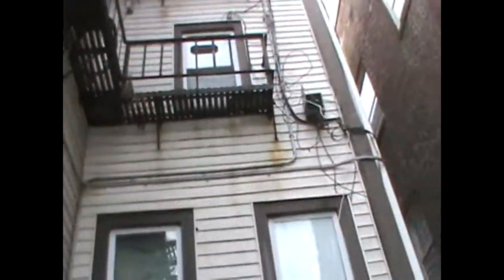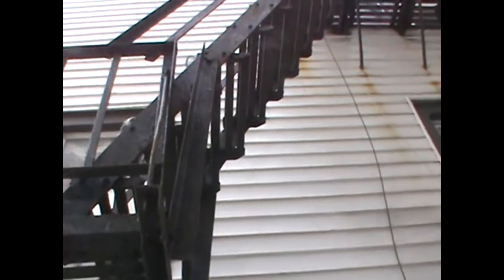So now look at these connections that hold the thing into the building. Any of these suspect? Sure. Okay. See all the rust in that corner? Yep. And that connection is holding up the entire staircase. So now you've basically got what you need on this fire escape, and that is that the fire escape has not been painted. So definitely the connections are suspect.